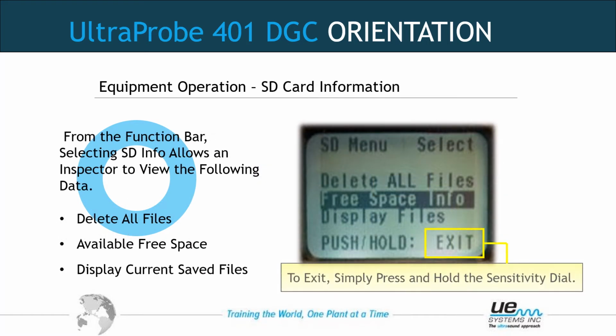The SD card information. From that function bar, you can choose SD card or SD info. Once you make the function bar flash and rotate until it says SD info, and you push and hold that sensitivity dial just a little bit longer than normal, it will pop you into here, which you have the options of deleting all the files of the SD card at once, or you can take the SD card out of the unit when it is off and put it into your computer and delete all the files. You can view the free space and info on the SD card or display all the files that are there, which will be all text files. To exit this, push and hold, and it will exit back out to the display you left.